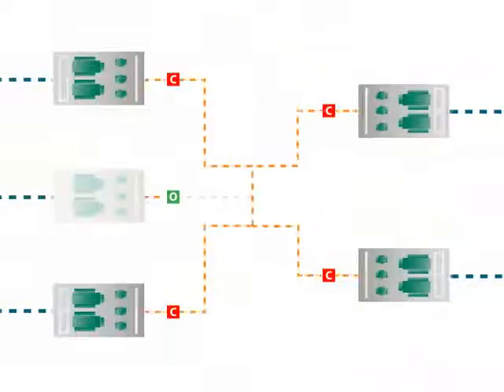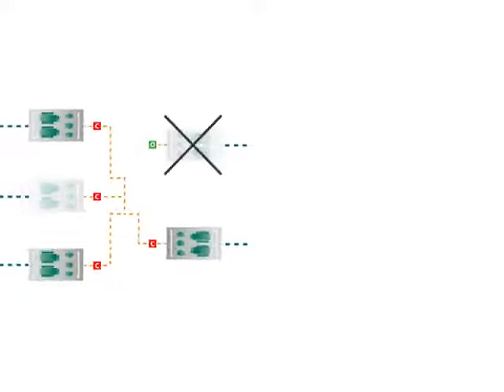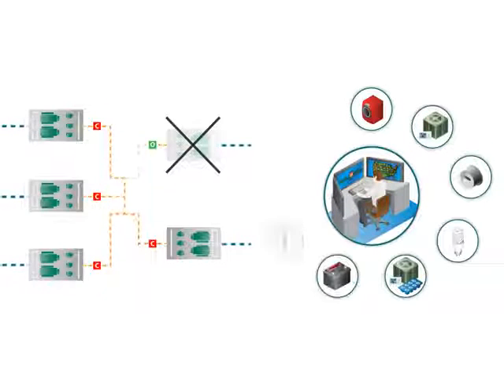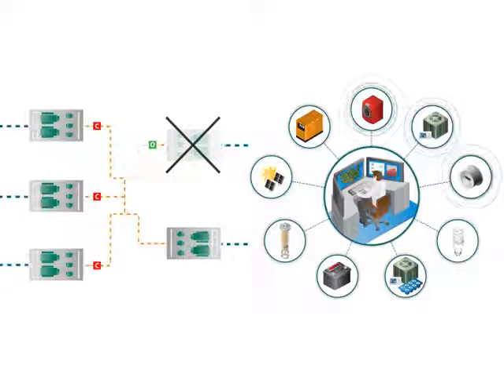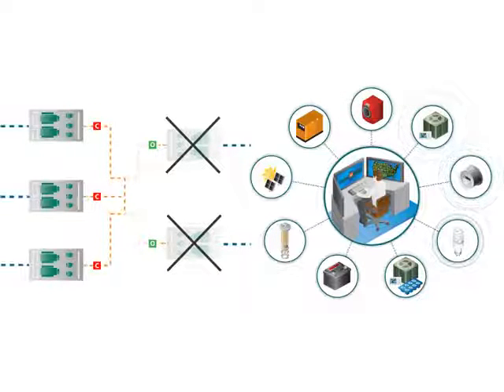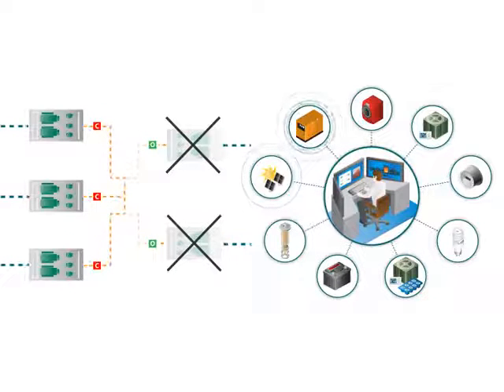So here's how this virtual power plant technology can be used to address an N-2 scenario. During an N-1 event, proactive communications to the virtual power plant puts those distributed resources at a high state of alert. Weather and demand forecasts are fed into an intelligent controller to determine the optimum dispatch scenario in the event of a second failure. When a second contingency event occurs, or N-2, the intelligent controller automatically reduces load in real time to reduce the risk of the remaining 3 transformers getting overloaded, using the virtual power plant resources if load exceeds the ability for the grid to meet the demand.